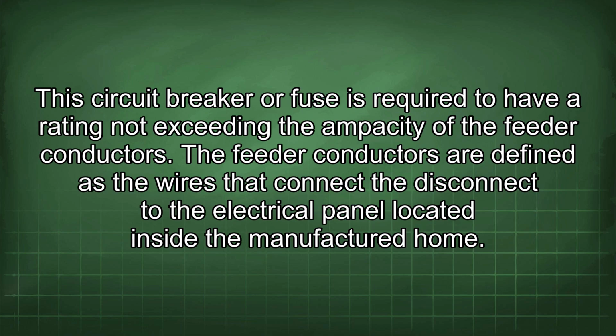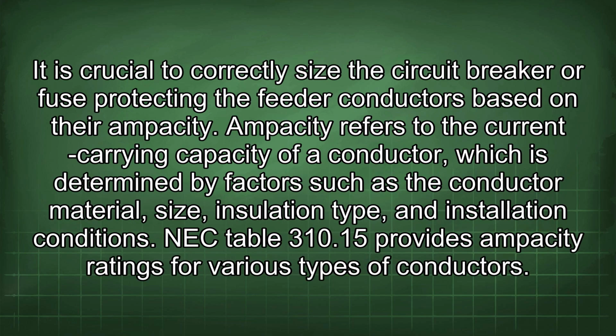The feeder conductors are defined as the wires that connect the disconnect to the electrical panel located inside the manufactured home. It is crucial to correctly size the circuit breaker or fuse protecting the feeder conductors based on their ampacity. Ampacity refers to the current carrying capacity of a conductor, which is determined by factors such as the conductor material, size, insulation type, and installation conditions. NEC Table 310.15 provides ampacity ratings for various types of conductors.